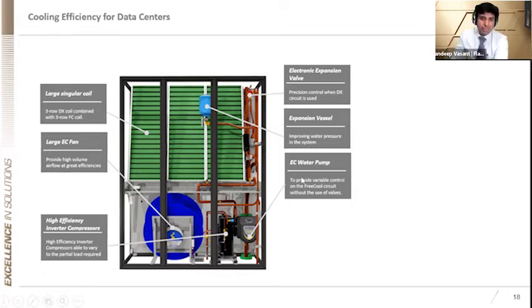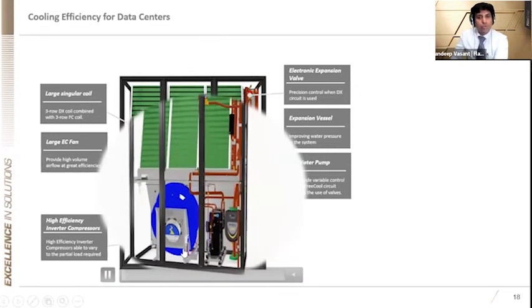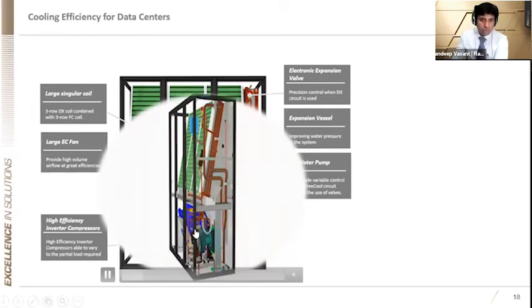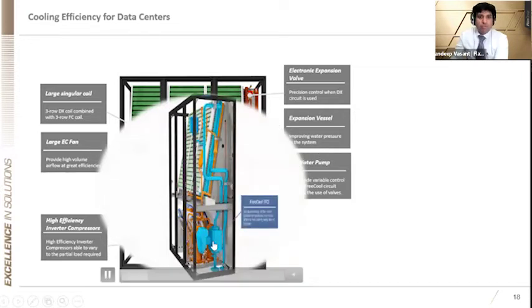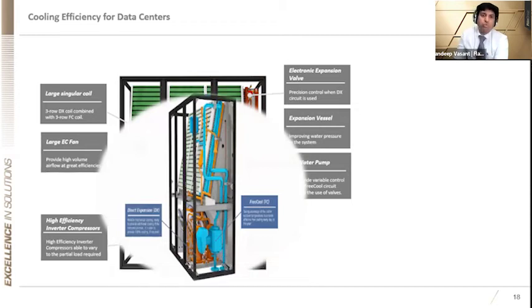So the same PAC that we saw would have another circuit. Here goes a short video of the working principle. The same cooling unit would have another circuit. One circuit would be direct expansion, chilled water or dual. There would be another circuit, a free cooling circuit. When I say free cooling circuit, it is circulation of water to a heat exchanger, a closed loop circuit. Along with that, you will have a direct expansion, chilled water or dual coil pipe as well.